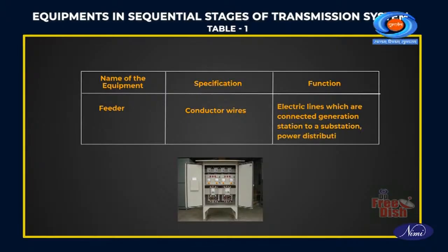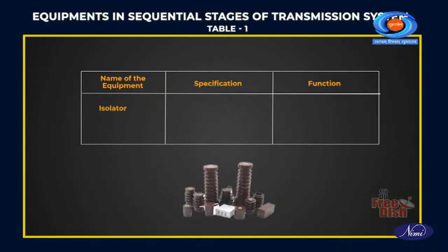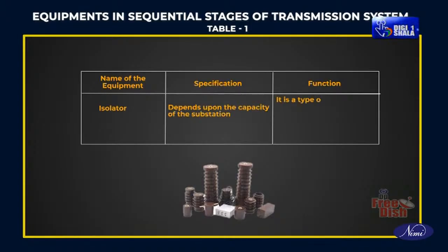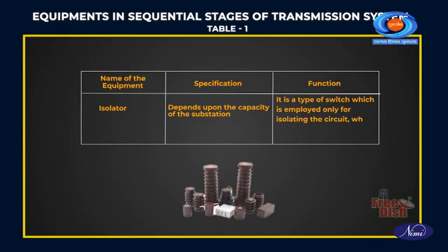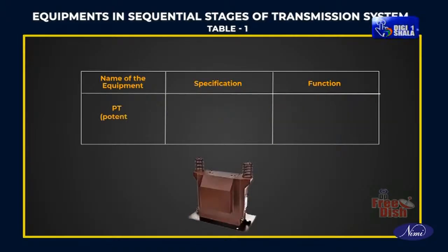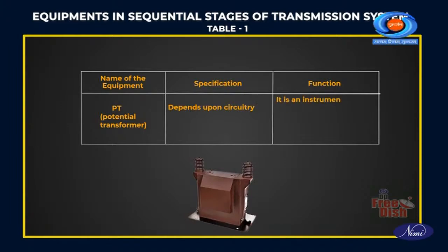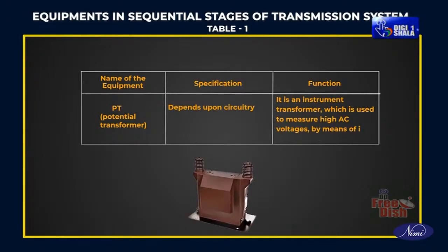Power distribution centers. Isolator. Depends upon the capacity of the substation. It is a type of switch which is employed only for isolating the circuit when the current has only been interrupted. PT or potential transformer. Depends upon circuitry. It is an instrument transformer which is used to measure high AC voltages by means of its proportionate lower values.